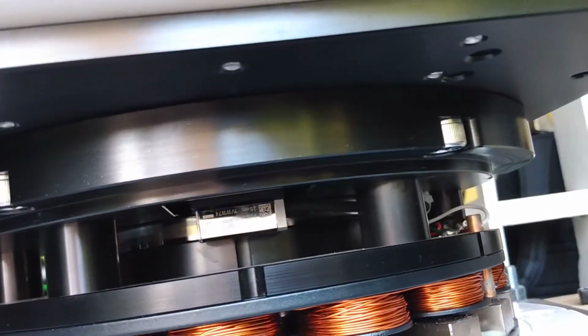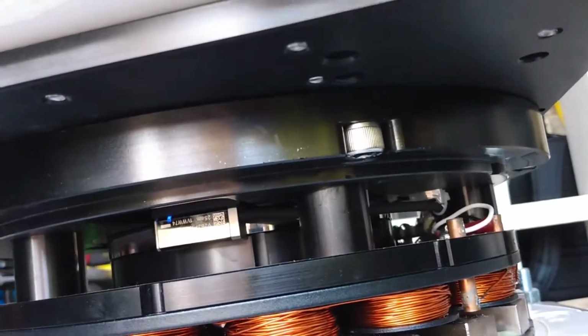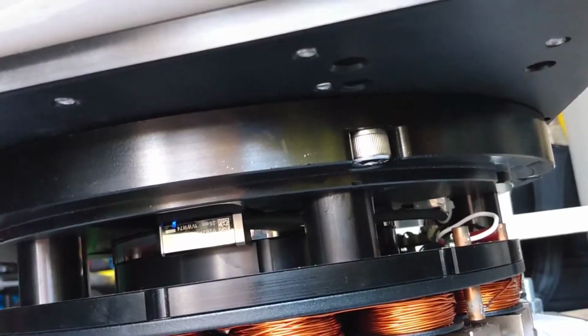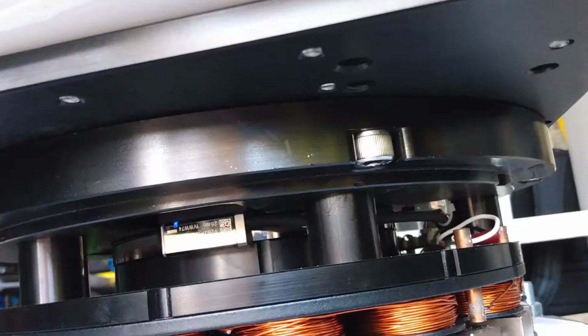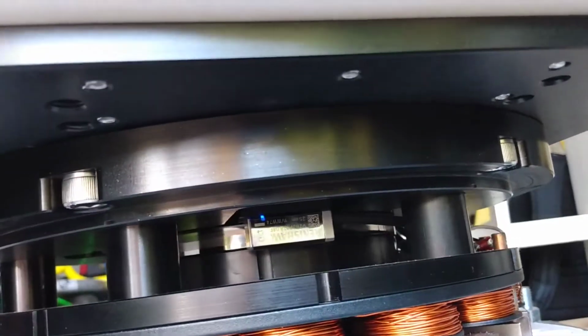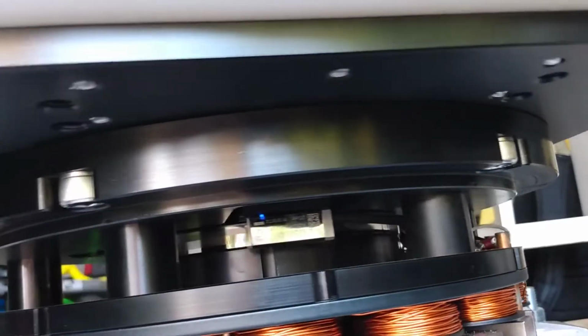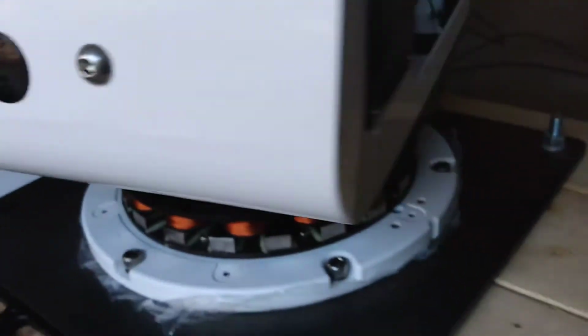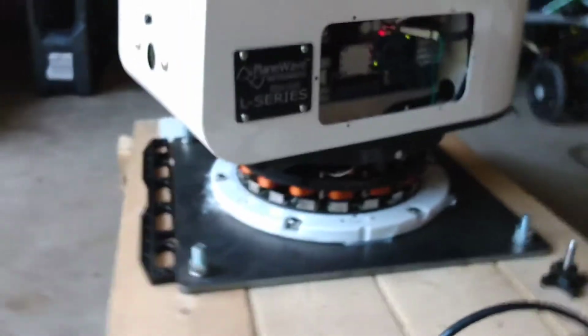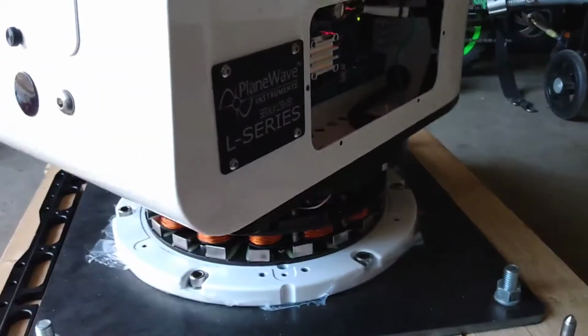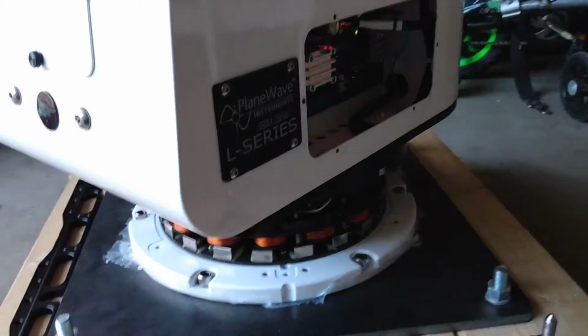You may need to go back and forth a few times, but when it's solid red or solid blue, that's when you know that it's calibrated. And then you can check it by going back and forth over that index position a few times and making sure that it flashes each time. You do want to start away from the index mark position when you're doing this calibration, just so that the index mark itself doesn't mess up the first step of calibration. So I usually recommend rotating about 45 degrees or more away from the index mark position.